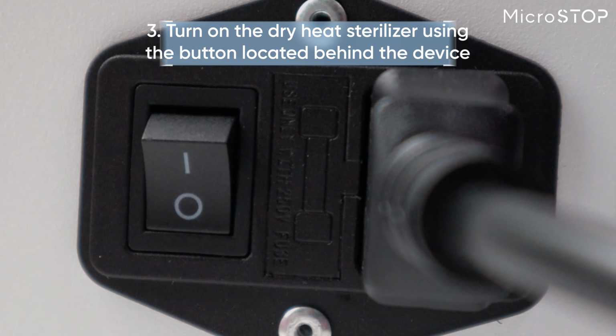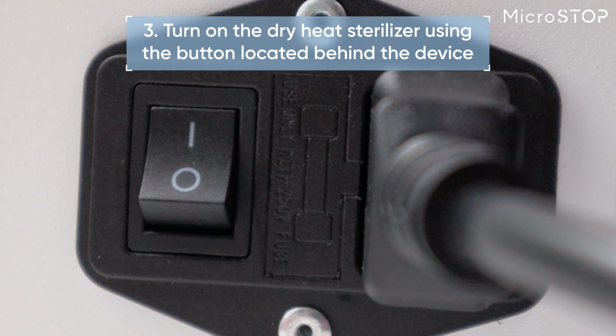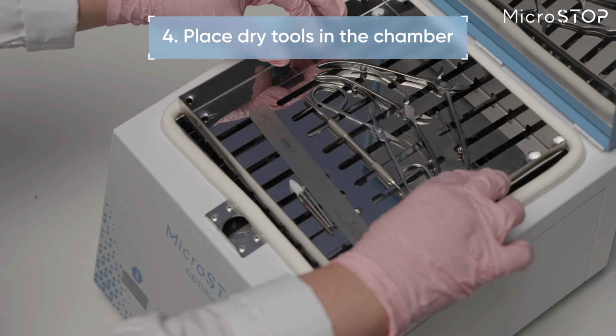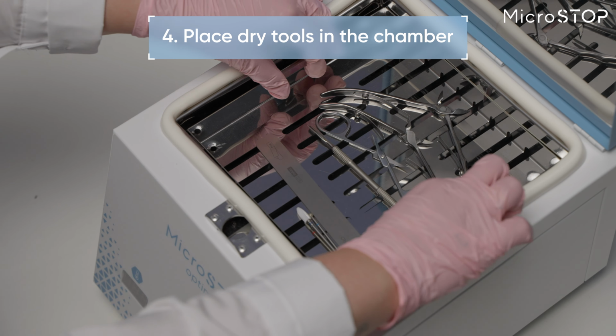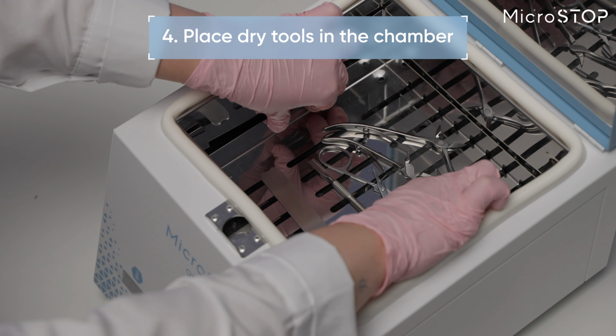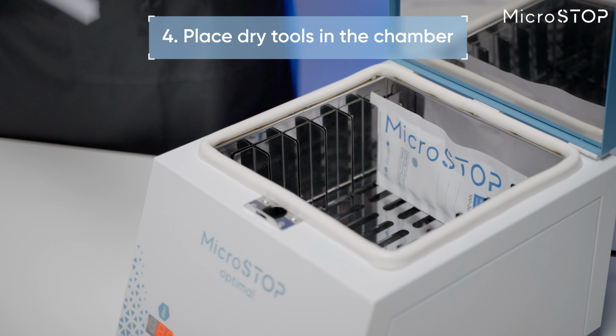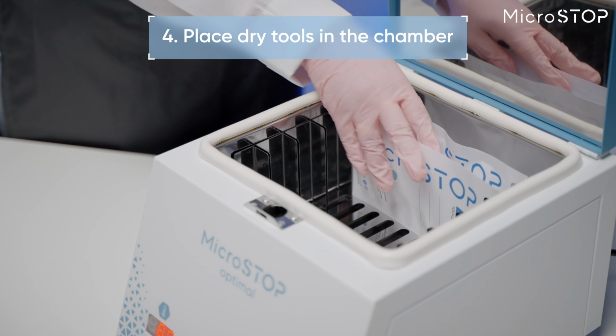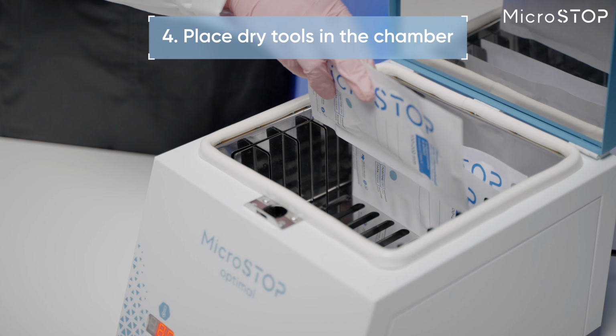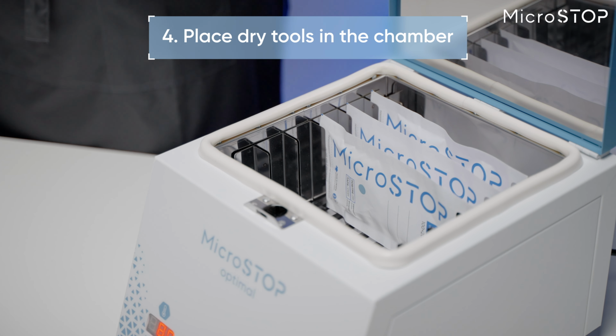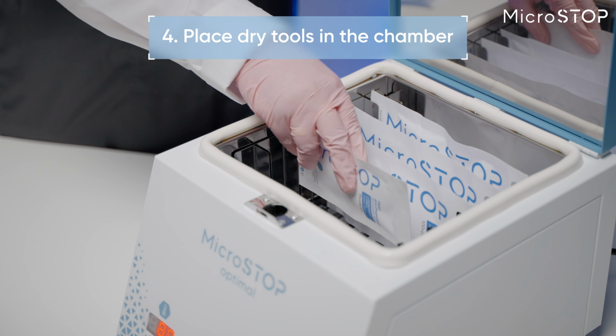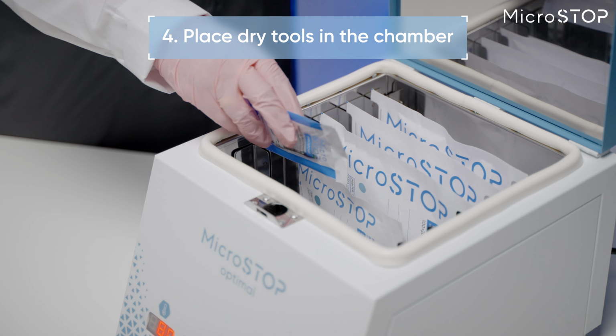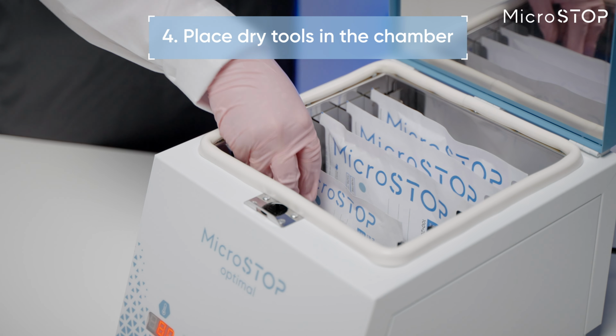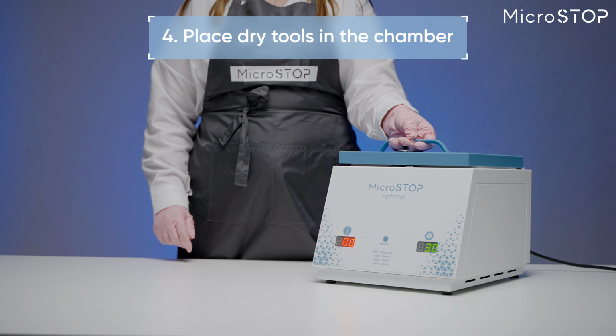Turn on the dry heat sterilizer using the button located behind the device. Place dry tools in the chamber. If you do not use kraft pouches, place them flatly on a metal tray. If you use sterilization pouches, place them upright in the holder. Important note, do not block the ventilation holes by more than 70%. Do not stack tools or sterilization pouches on top of each other during sterilization, as this prevents the hot air circulation.